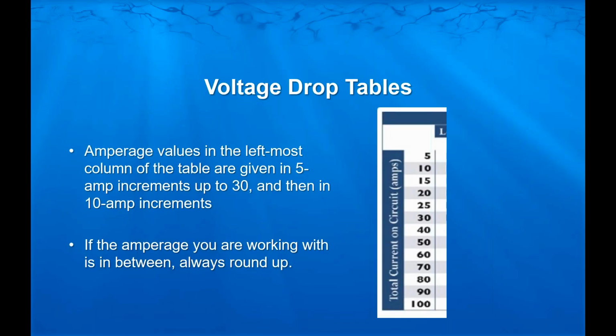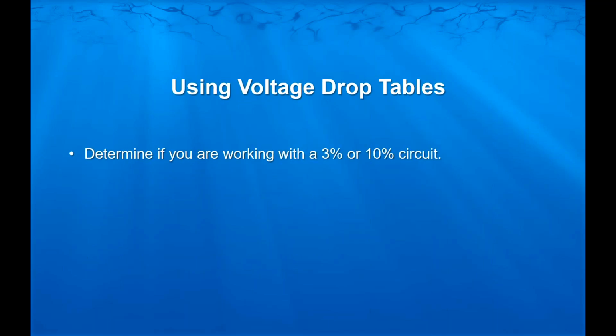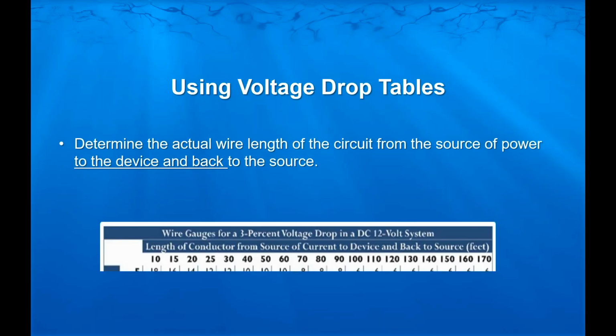On the left-hand side of the column, the amperage values are listed, and they're given in 5 amp increments up to 30, and then also in 10 amp increments. So if your amperage falls between one of those, or two of those numbers, you've got to go to the next highest one as your reference point. So in using the voltage drop table, the first thing you need to do is determine what kind of circuit you're working with. Do I need a 3% voltage drop or 10% voltage drop? And then you reference either the 3% or 10% volt drop table. So determine your actual wire length, the actual wire length from the source of power to the device and back.